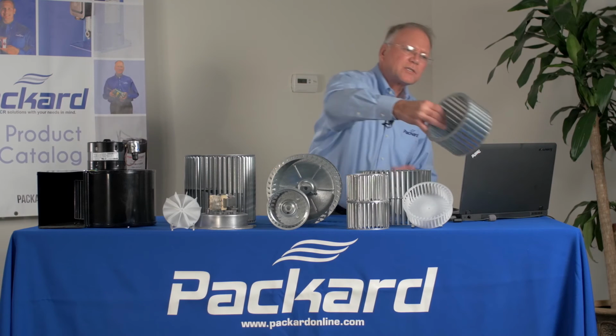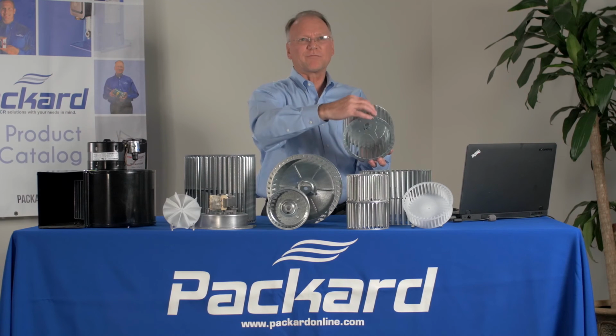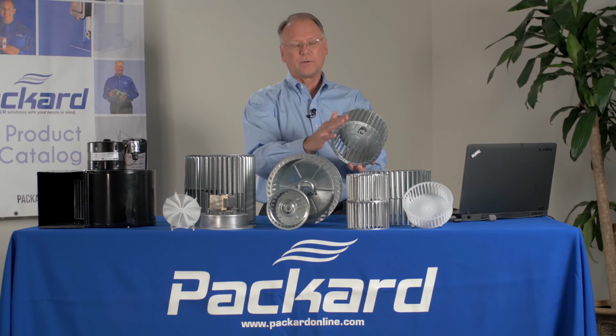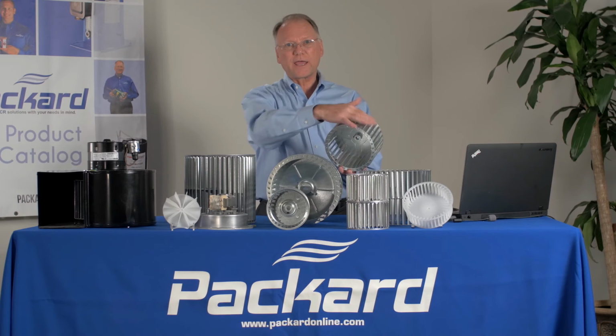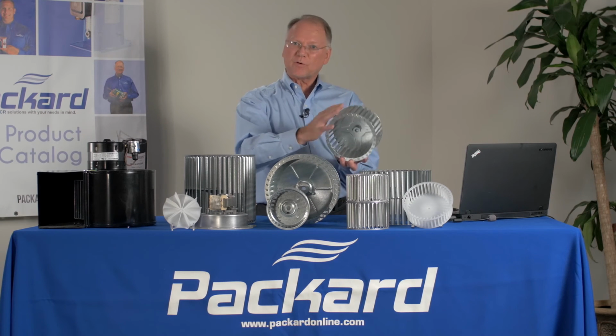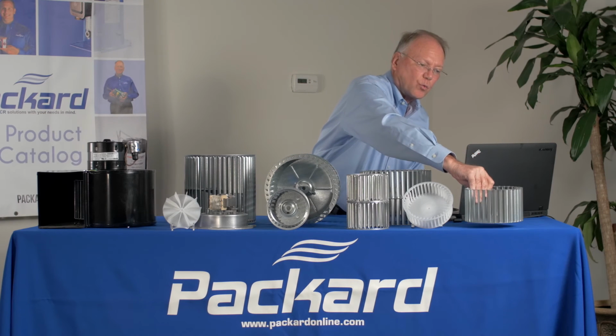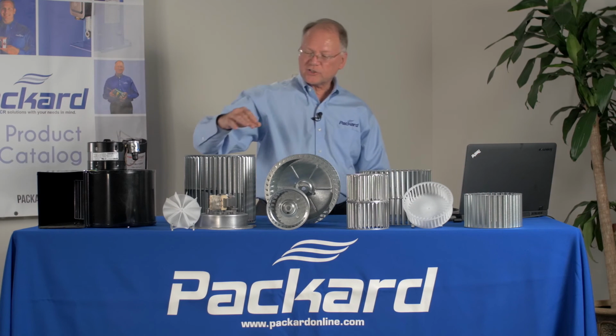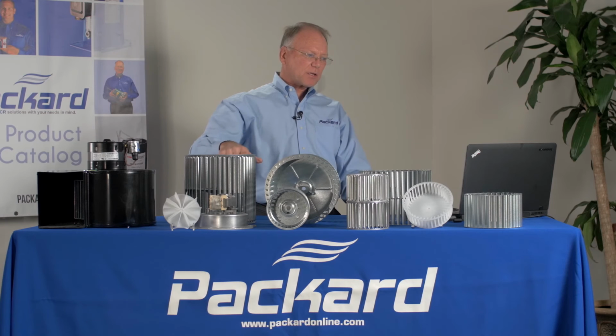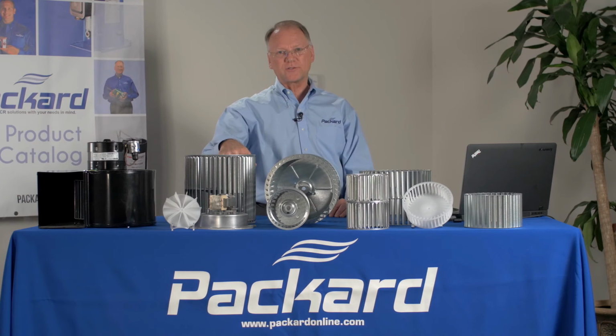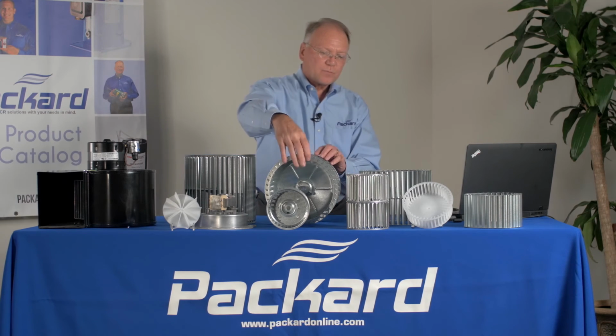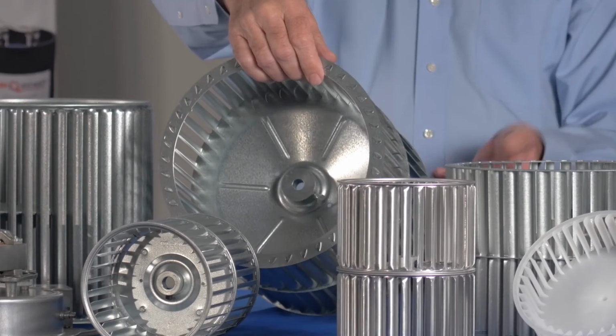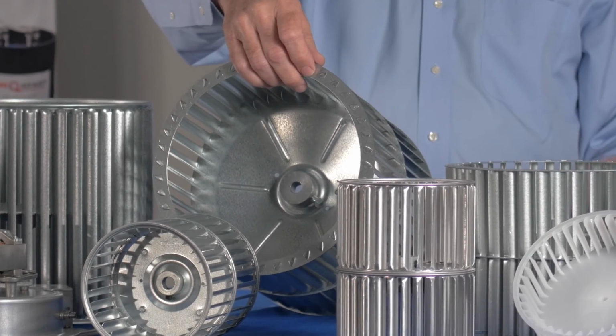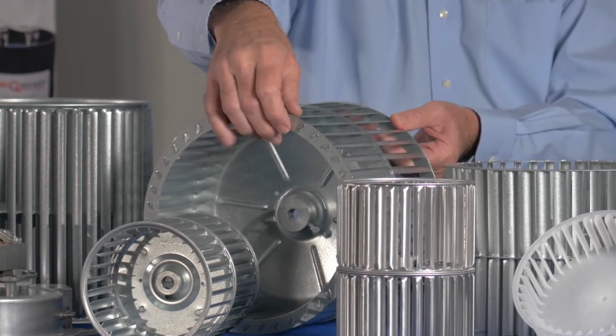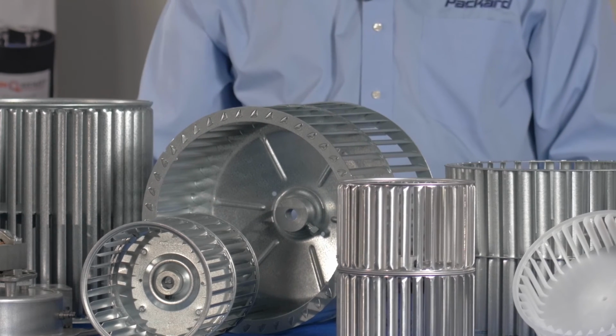Determining performance is also based on the number of blades within the wheel. Counting the number of blades will determine the performance of that given wheel. On a strip wheel, typically you can see 20 to 40 blades on a wheel. On a tab lock wheel, you can get more blades, which provide more air, more pressure. You could see 24 to 64 blades.